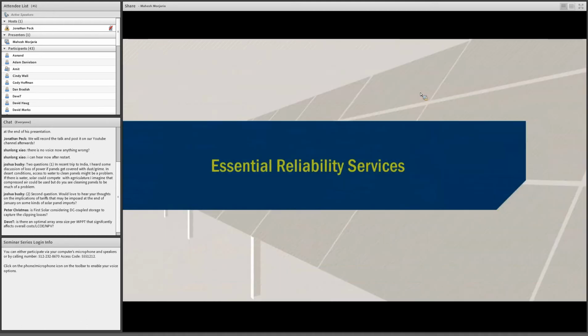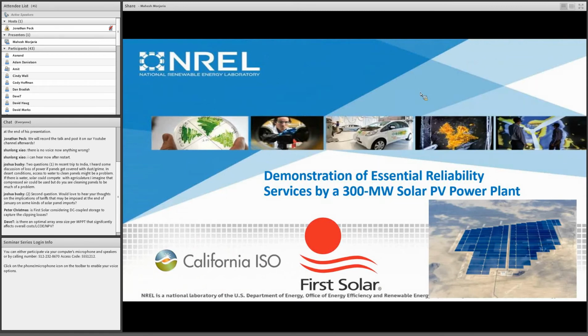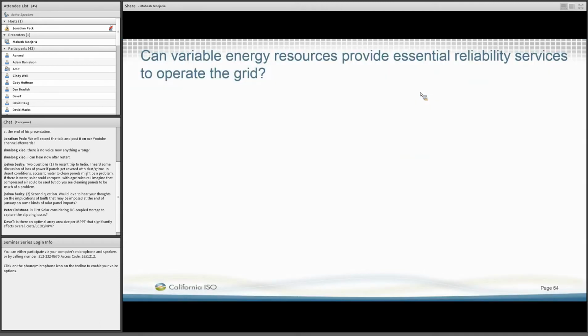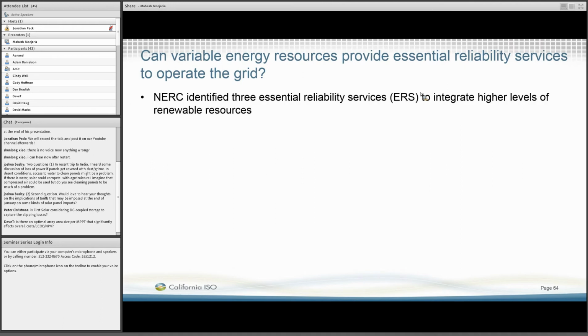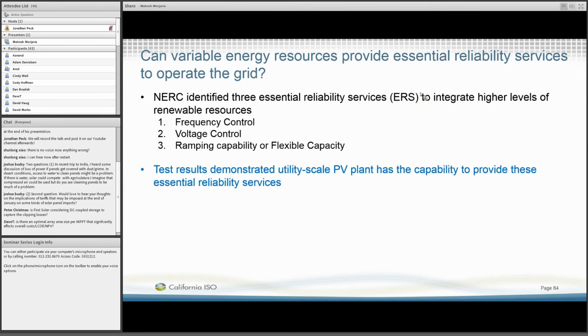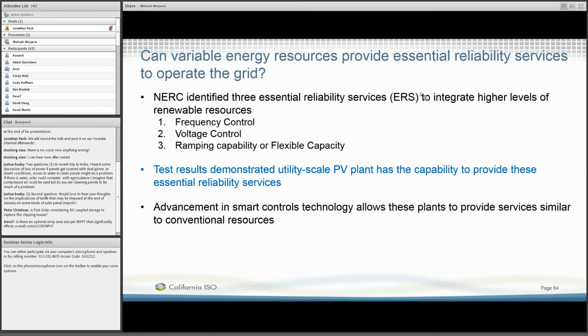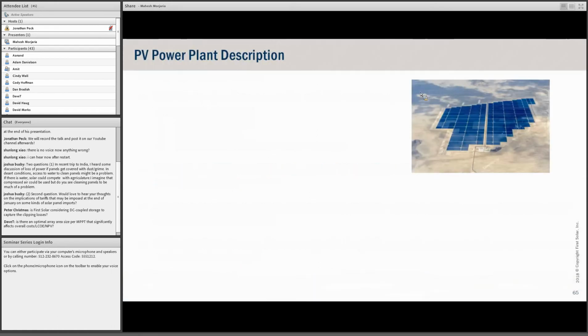That's the bottom line. Recently we had a question about essential reliability services. We ran a demonstration with the CAISO and NREL on a 300 megawatt solar plant. And the question was, can a PV plant provide reliability services? And particularly, NERC has identified frequency control, voltage control, and ramping capability or flexible capacity as being the necessity for providing reliability services. And certainly I'll show you some of the test results. And indeed, those plants can provide those capabilities. Not only that, but it actually can do a very good job of that. Now I'm running out of time, so I'm running it a bit fast.